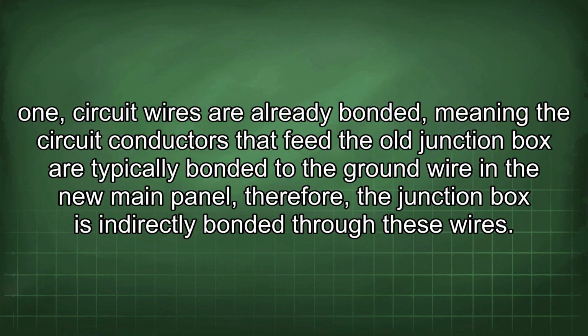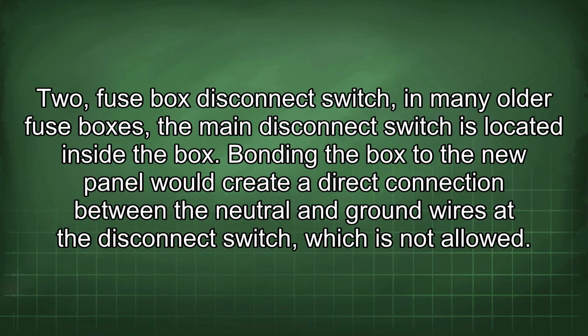1. Circuit wires are already bonded, meaning the circuit conductors that feed the old junction box are typically bonded to the ground wire in the new main panel, therefore the junction box is indirectly bonded through these wires. 2. Fuse box disconnect switch. In many older fuse boxes, the main disconnect switch is located inside the box. Bonding the box to the new panel would create a direct connection between the neutral and ground wires at the disconnect switch, which is not allowed.